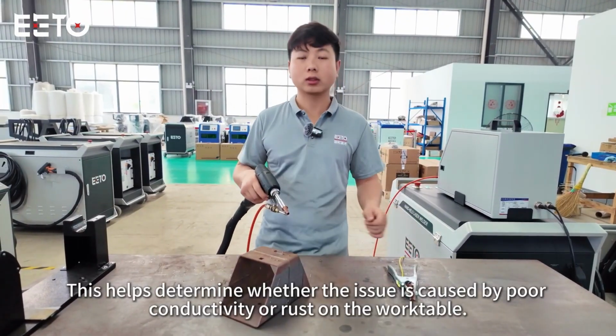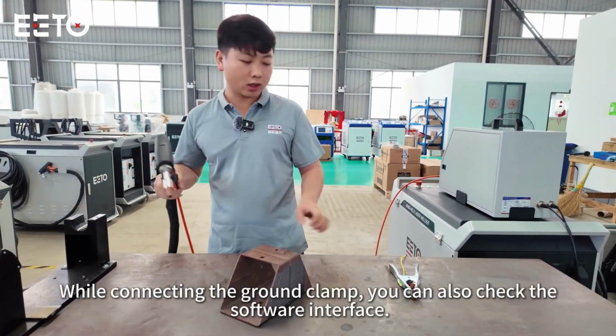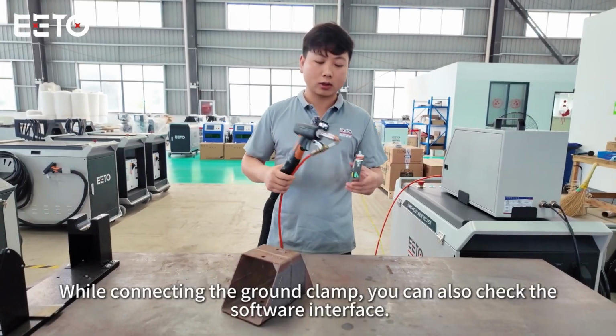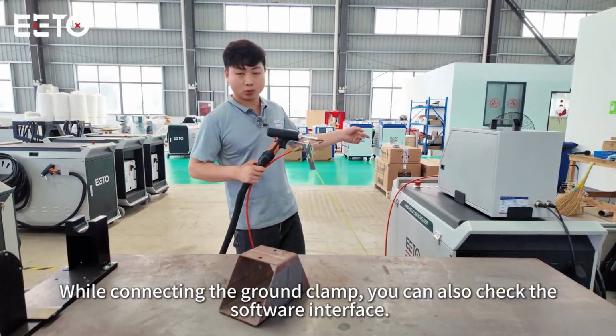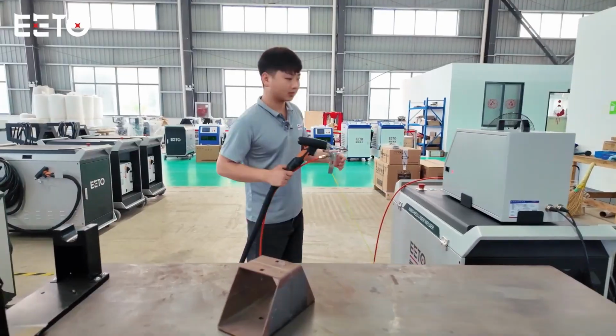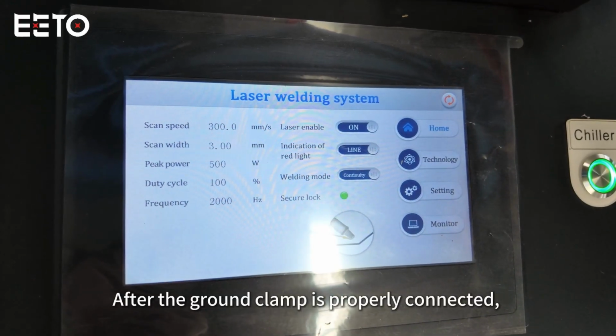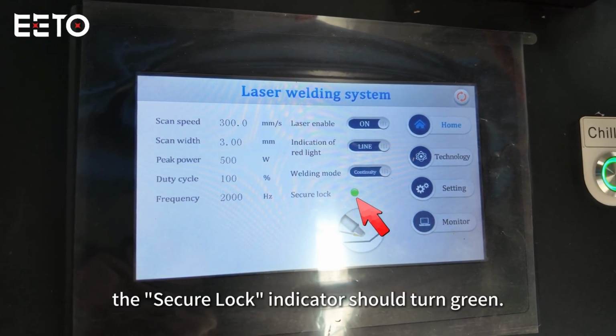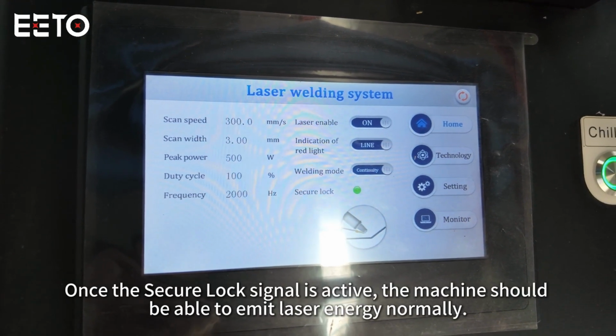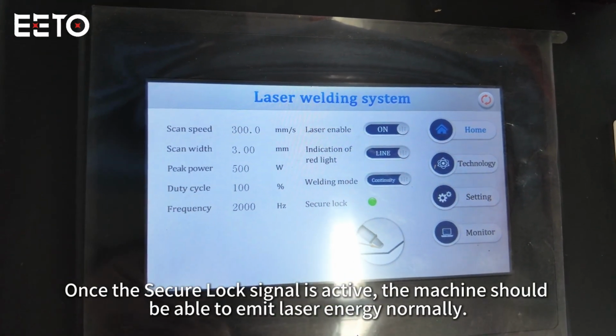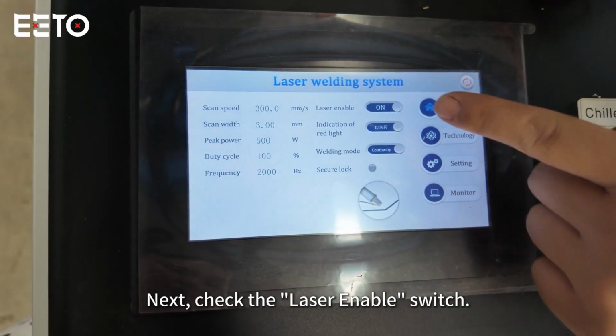While you are connecting the ground clamp, you should also check the software interface for any status updates. After the ground clamp has been properly and securely connected, the status indicator will update to show a stable connection. The secure lock indicator should turn green. Once the secure lock signal is active, the machine should be able to emit laser energy normally.